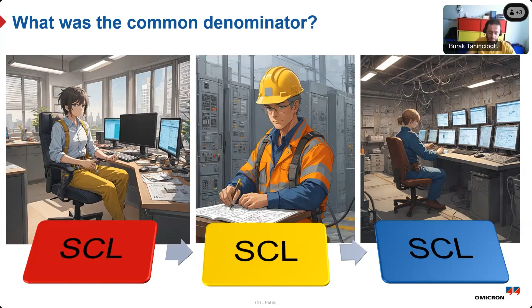So why do we need to make an IEC 61850 specification? Because we need to have full control over the project as a utility, and know what's going to happen at the end of the specification and configuration phase, aligned with our project requirements. We want to build more and more typical substations nowadays, and that will be the first step for top-down engineering.